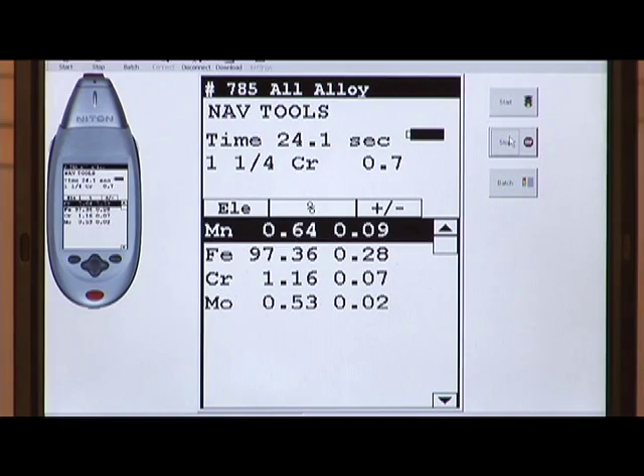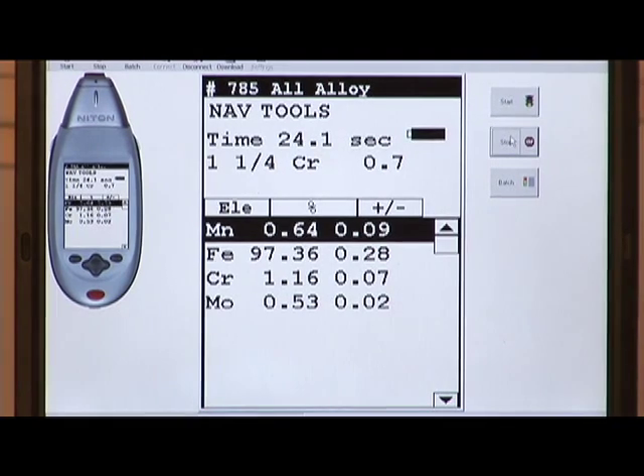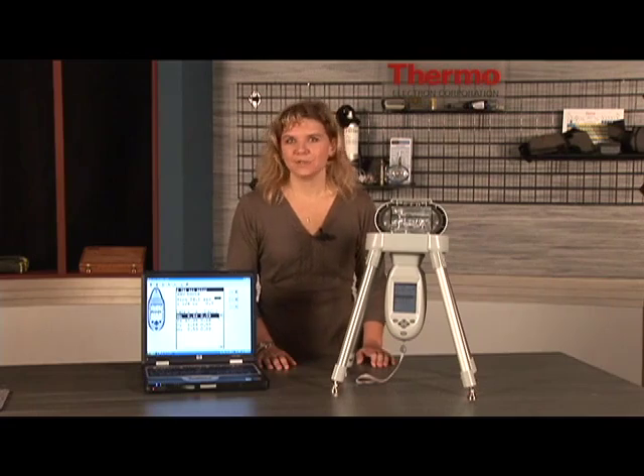As we can see from the results for each element, we are now within the boundary conditions that we established previously, including the moly reading, which is now within 1/100th of the upper limit, when we include the 0.01% error from the certificate. If your check sample reads correctly as well, you're ready to test unknown samples. This is the end of Module 2. Module 3 will cover the measuring of unknown samples.